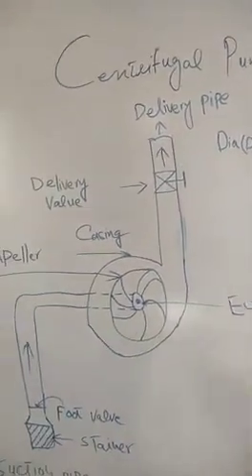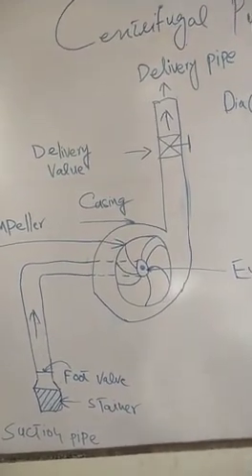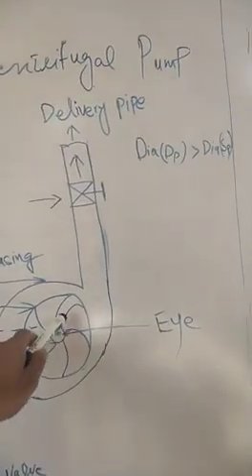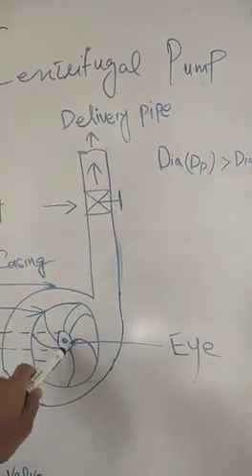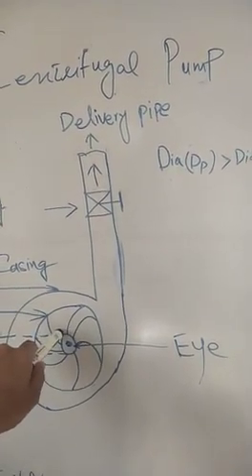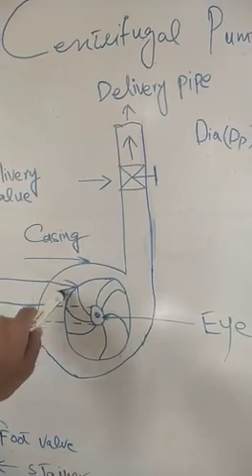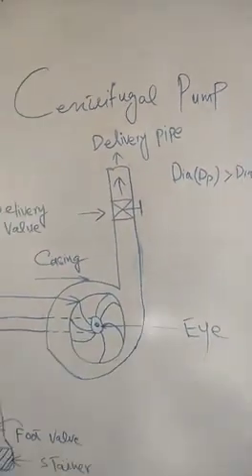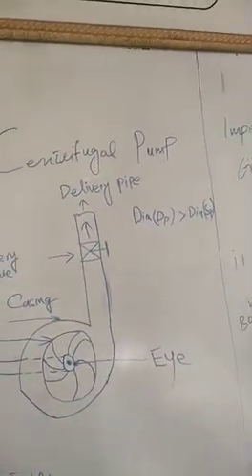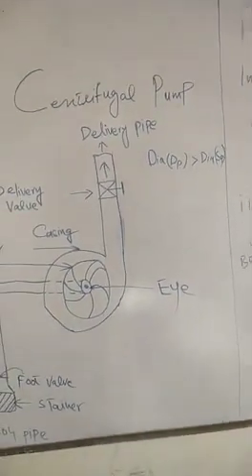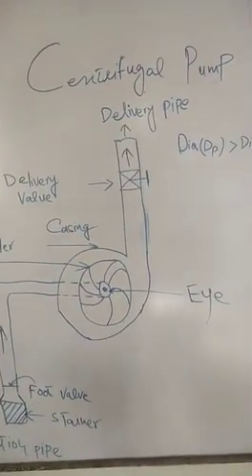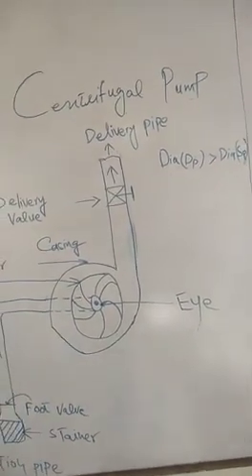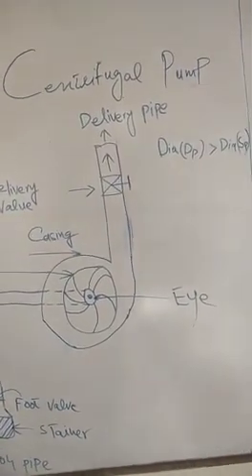The impeller concept is now clear. When water comes from the suction pipe into the impeller, it first enters through the eye (inlet). The eye directs the water into the vanes. As the impeller rotates, water passes through the casing and goes forward into the delivery pipe. The diameter of the delivery pipe is larger than the suction pipe, which reduces the velocity and thereby increases the pressure of the water.